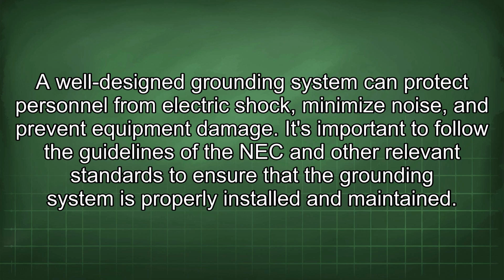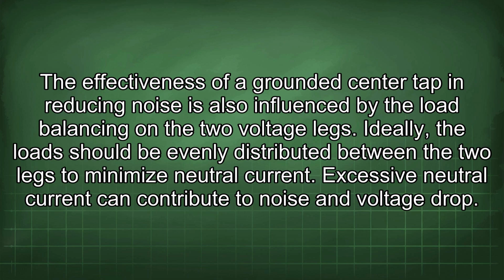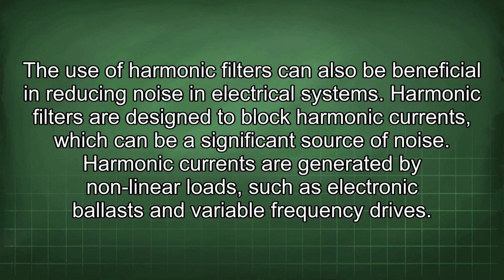The effectiveness of a grounded center tap in reducing noise is also influenced by the load balancing on the two voltage legs. Ideally, the load should be evenly distributed between the two legs to minimize neutral current. Excessive neutral current can contribute to noise and voltage drop. The use of harmonic filters can also be beneficial in reducing noise in electrical systems. Harmonic filters are designed to block harmonic currents, which can be a significant source of noise. Harmonic currents are generated by nonlinear loads, such as electronic ballasts and variable frequency drives.